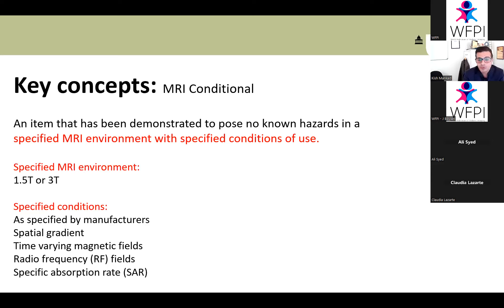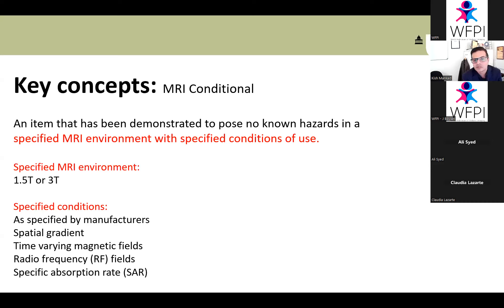MR Conditional is an item demonstrated to pose no known hazards in a specified MR environment with specified conditions of use. The specified environment might be 1.5, 3, 7 Tesla or less, and the conditions can be numerous — listed under the yellow triangle label. Being MR Conditional is a relative state; it doesn't apply to all environments and conditions. It is specific to each piece of equipment, including fire extinguishers, oxygen cylinders, syringe drivers, or monitoring devices.